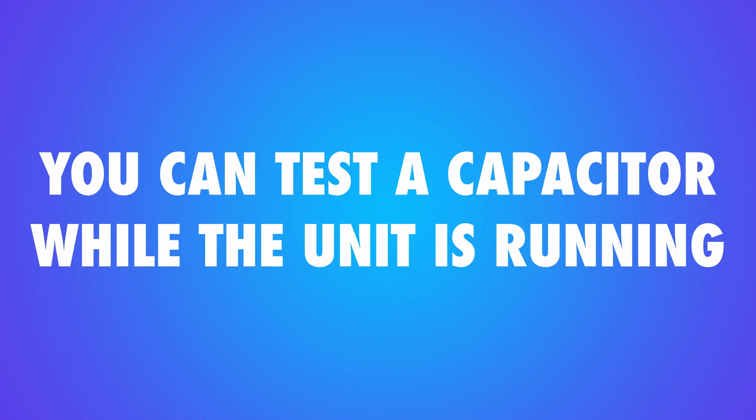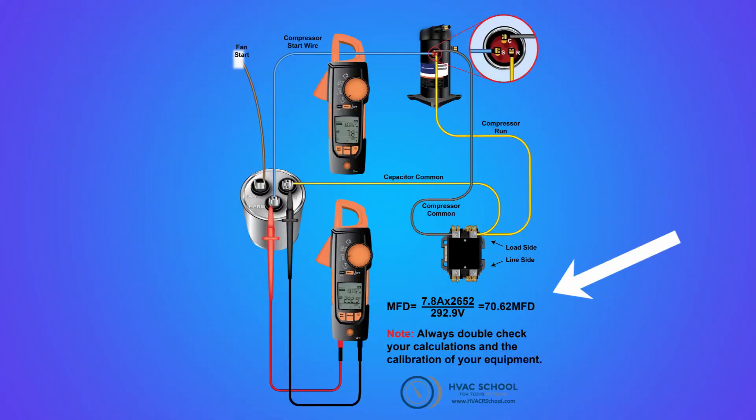You can test a capacitor while the unit is running. You simply measure the current or amperage of the motor start winding coming off of the capacitor and multiply it times 2652 on 60 hertz power and 3183 on 50 hertz power. Then you divide that number by the voltage you measure across the capacitor to come up with your microfarad value.